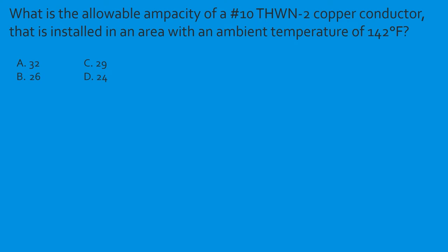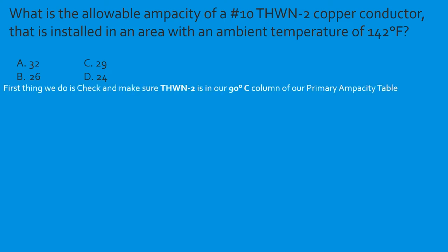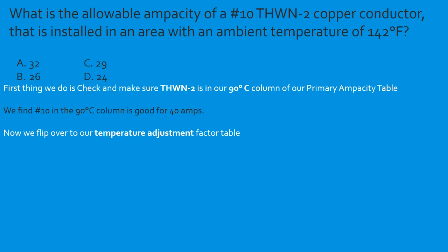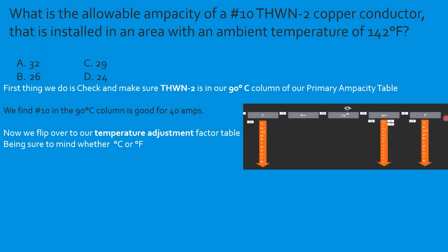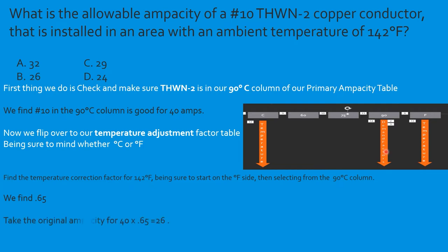Question: What is the allowable ampacity of a number 10 THWN-2 copper conductor installed in an area with an ambient temperature of 142°F? THWN-2 is in the 90°C column. Number 10 in the 90°C column is good for 40 amps. Go to the temperature adjustment table, start on the Fahrenheit side, find 142°F, tee off with 90°C — correction factor is 0.65. So: 40 × 0.65 = 26 amps. Select B.